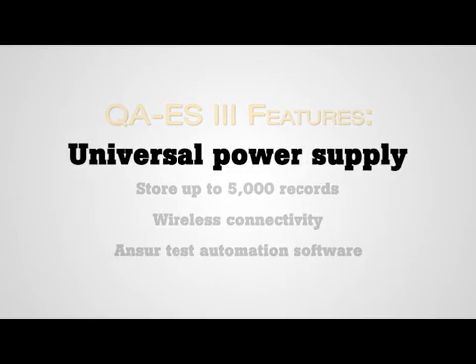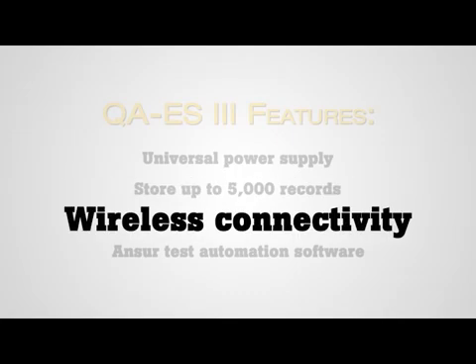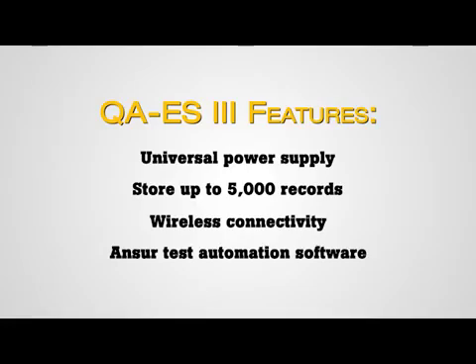Featuring a universal power supply and in compliance with global standards for testing electrosurgical devices, including IEC and ANSI/AAMI, the QA-ES III can be used worldwide. It can store up to 5,000 records, making it convenient to store results and retrieve later. Its Bluetooth wireless capabilities make it possible to quickly and conveniently transfer results to a PC. The addition of Ansur software further automates and standardizes testing, speeding up overall test times and minimizing human error.